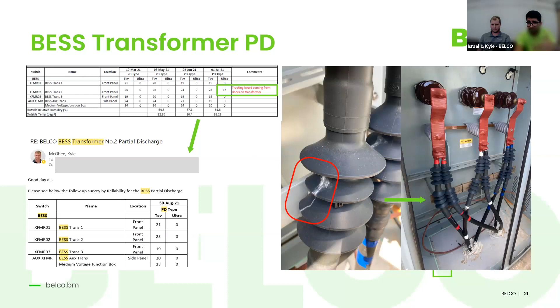So in this case, it's a pretty simple fix. You clean off all the partial discharge product, you rearrange your fastening arrangement. In this case, we put an insulating spacer between the cables and the frame, and then we put it back together. So we found that improper installation, we found those signs of corona discharge, and it was a simple resolution to the issue. The discharge subsided from that point.